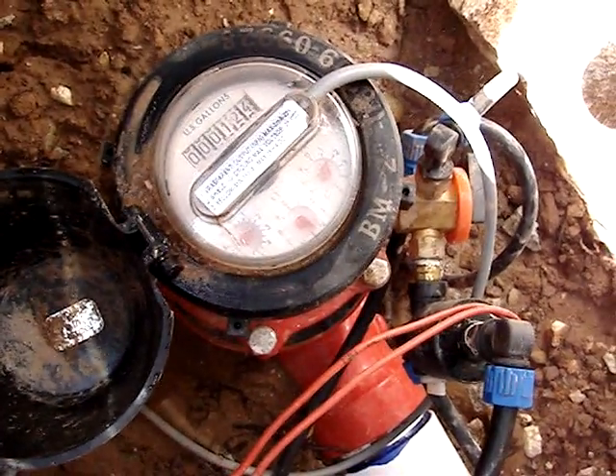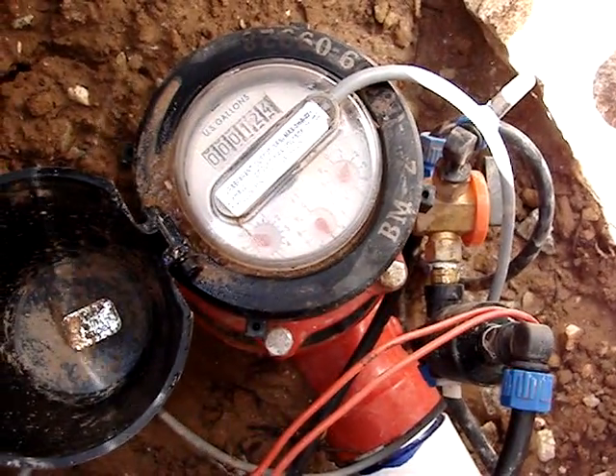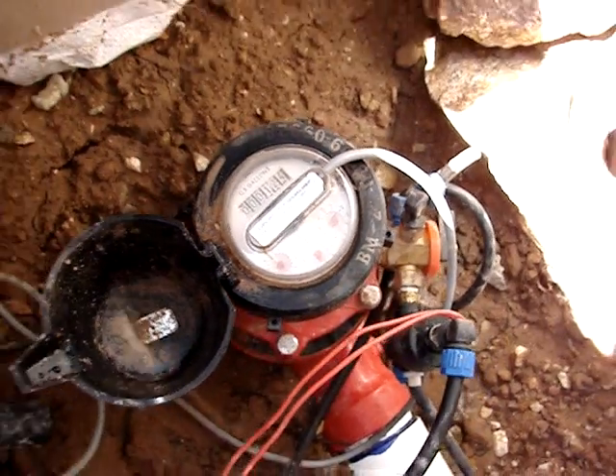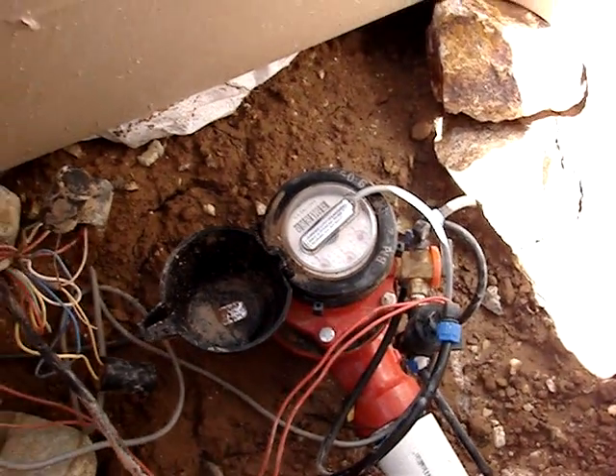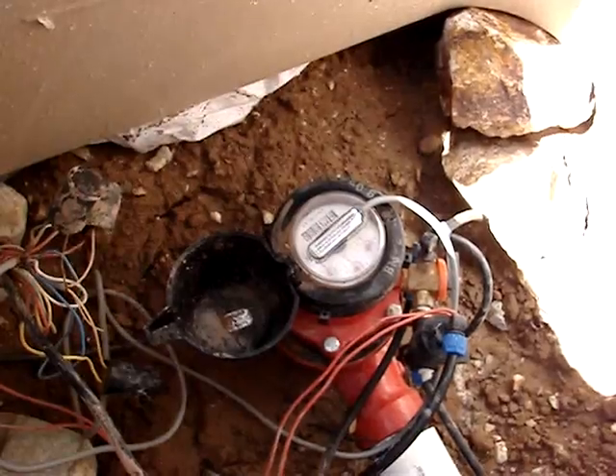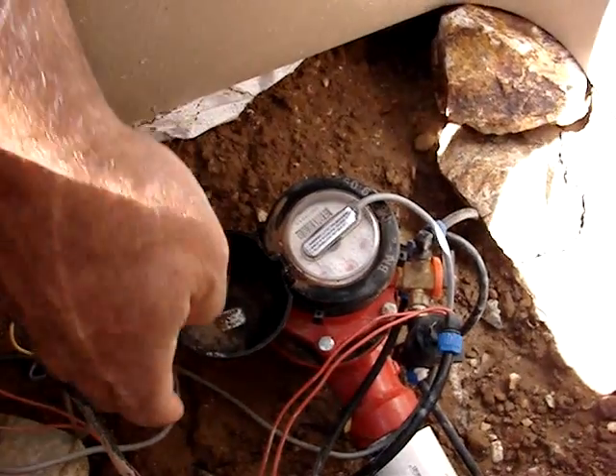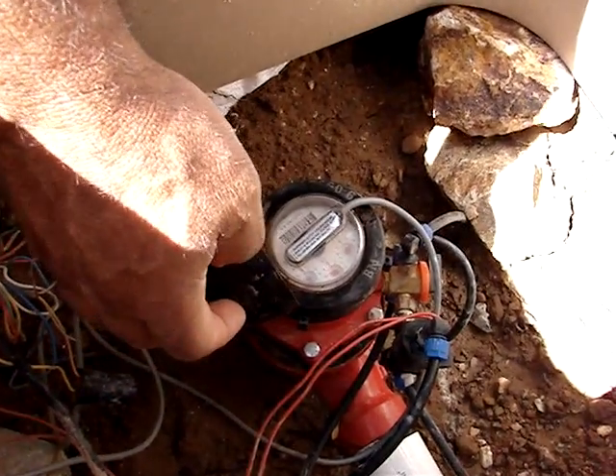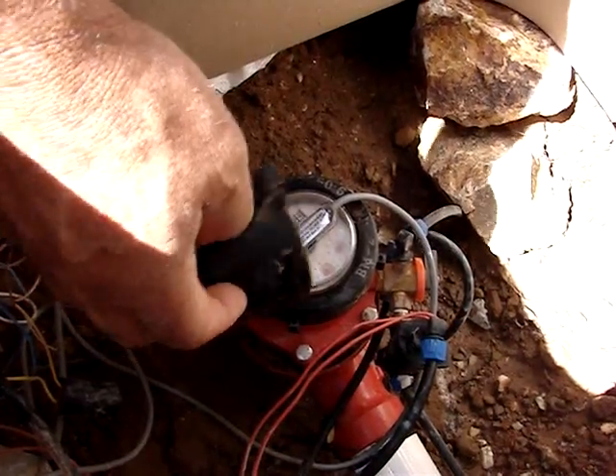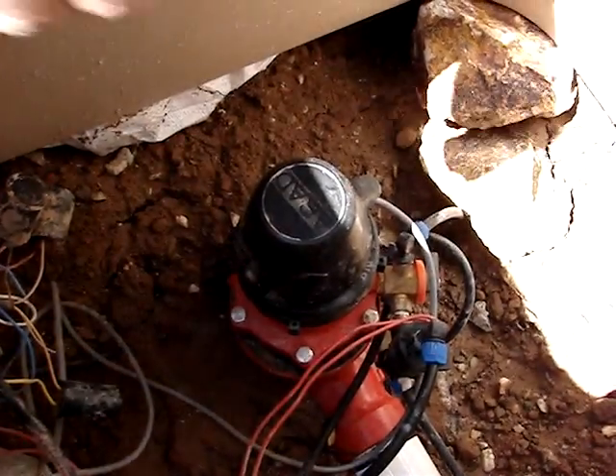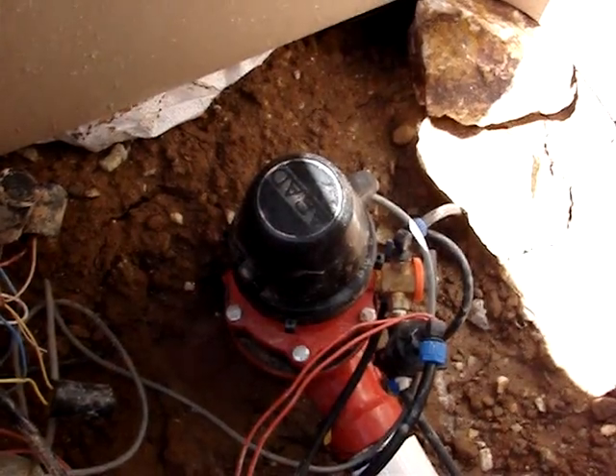And there you go. Now, one other key thing here is that this is a photodiode, which means that there's a little light beam that's being broken, and that's how we create the pulse for the clock. So if there's light out, the clock may not read it unless the cap is totally closed to prevent light from interfering with that photodiode. So we keep the cap closed.